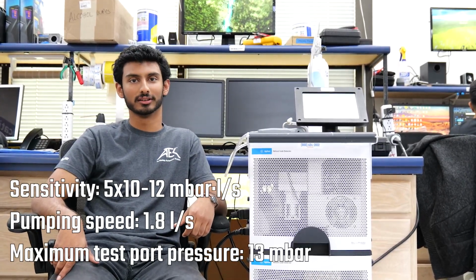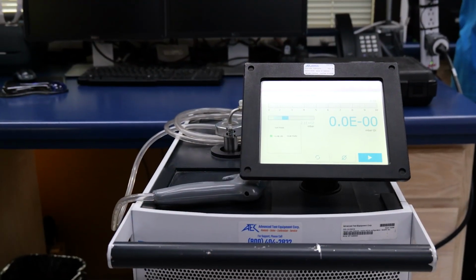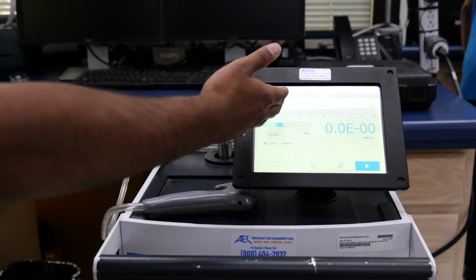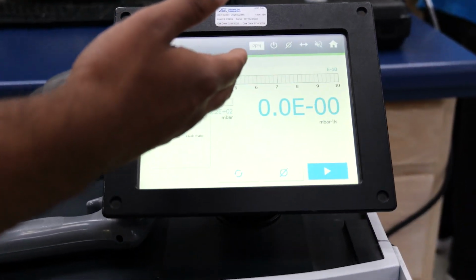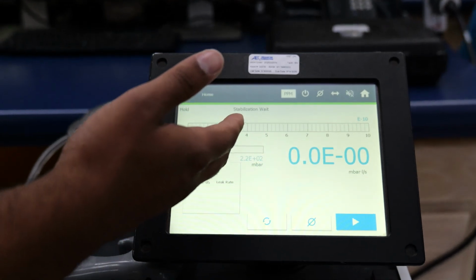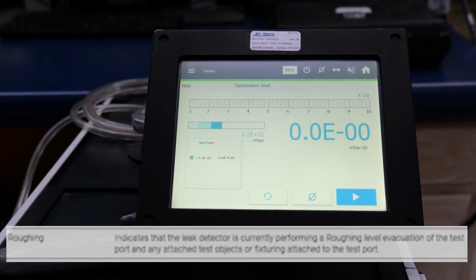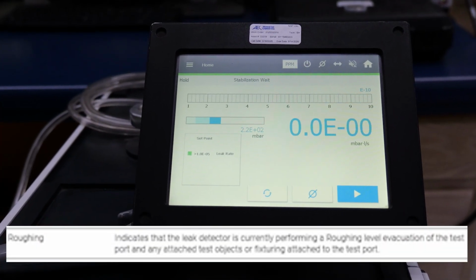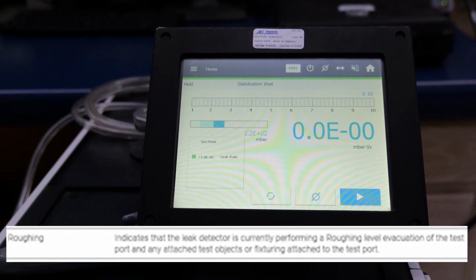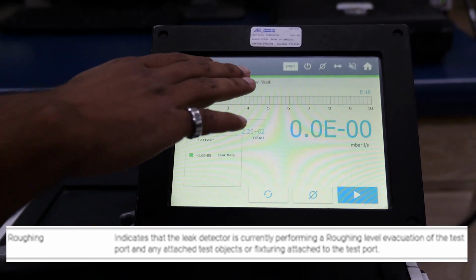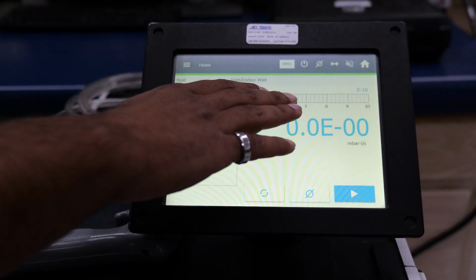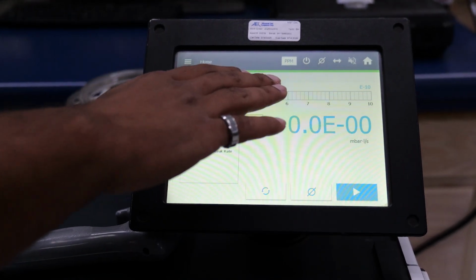Once you've turned on the helium leak detector, you should be seeing prompts for stabilization wait, or some form of waiting for the actual roughing pump and turbo pump to build up the vacuum pressure inside. And at some point, usually within 30 minutes, you should see a system ready prompt.